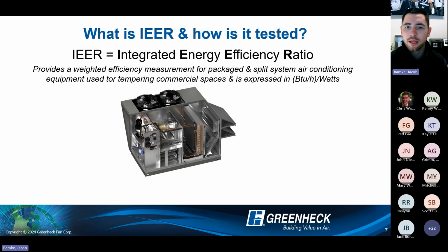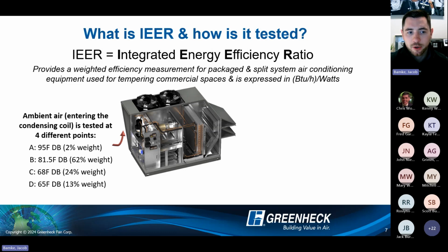And the first one that we're likely a little bit more familiar with is our IEER. This stands for Integrated Energy Efficiency Ratio, basically looking at 4 different conditions. So here we have point A, B, C, and D. They're weighted differently. With these 4 outdoor conditions, I have an EER value that I can calculate from each one of these conditions. So for example, I would take the EER value at point A, times 0.02, and then combine that with the value from point B times 0.62 and get one integrated value.